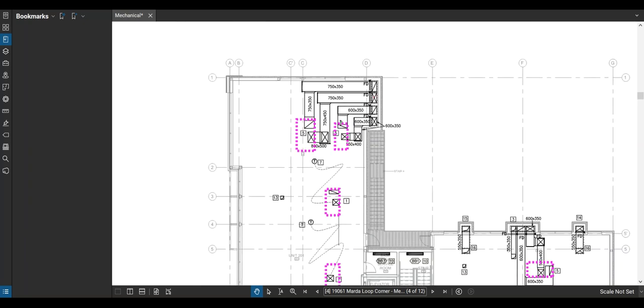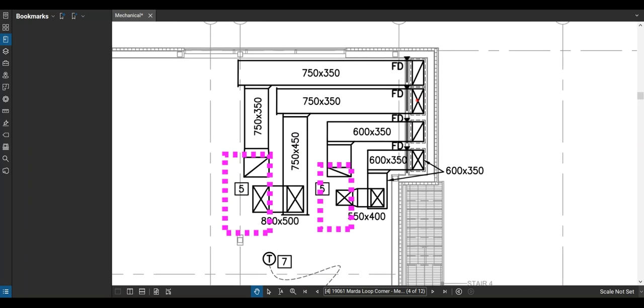Going over to this corner, when you see an X through something, that is a vertical section of a supply duct. The supply air from this unit on the roof is coming down right here and goes horizontal this way, then it looks like it drops down again and goes horizontal, then drops down again. What's happening is the supply air from that unit is coming down from the unit through the roof, then there's a horizontal duct, and it probably has to drop down again to get underneath some roof joists or structure. These ducts would be in the ceiling of this tenant — a 750 by 450 deep duct.